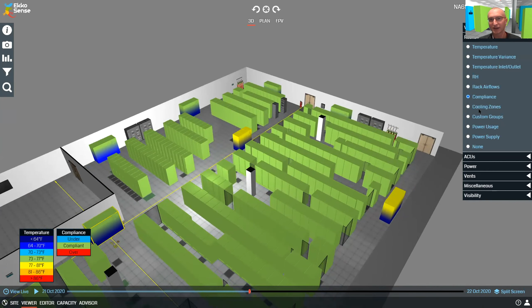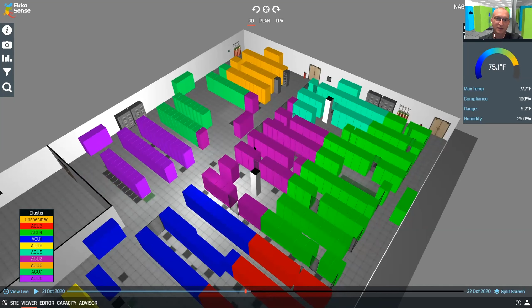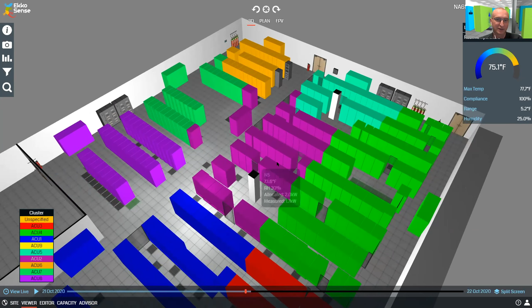And we can do that because we're looking at the trends over time. We're looking at all that data that we're collecting from the racks, and this is dynamic. So any changes that are being made as you're putting new racks in, as you're moving floor tiles around, if you're making changes to air conditioning units, this zone of influence essentially will update. So you can actually know which racks are going to be affected by any maintenance that you may be passing out an air conditioning unit, or if you need to have an air conditioning unit off, or if it's going to fail, you know exactly which racks are most likely to be affected.